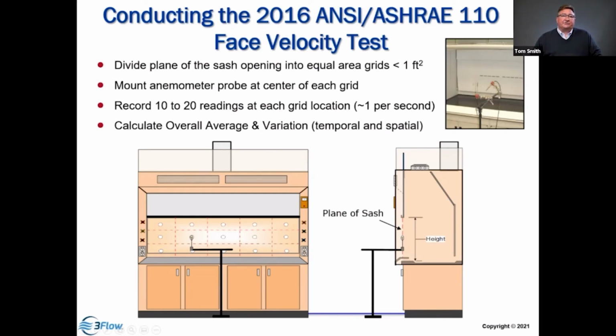At the center of each grid, we're going to place the probe to measure the velocity at the center of each grid. And that should be in the plane of the sash. So if we were to draw a line from the top of the sash to the work surface, that is our plane of the sash, and our probe should be aligned directly in the plane of the sash. When you're hand holding the probe, as you are looking at your meter and so forth, you can move that probe out of the plane of the sash and introduce error. And in addition, you need to mount it in the same location every time because of accuracy and precision.